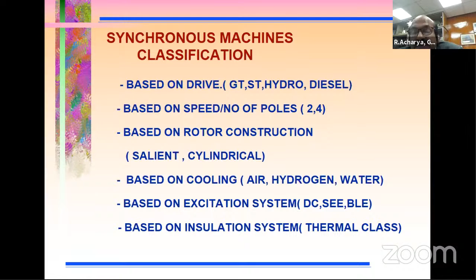Based on the excitation system, whether it's DC, which is an old system, or a static or brushless system. And based on the insulation system - the topic I'm trying to highlight - it's based on the thermal class of insulation. So machines are designed whether class B or class F or whatever, and most utilities operating large capacity machines basically use class F insulation systems.